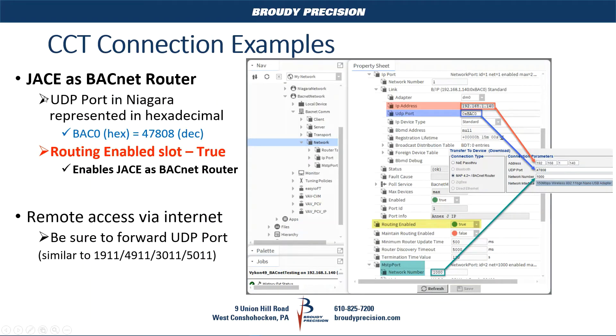If you're going through a JACE, first make sure routing is enabled on the JACE. There is a slot for that under the network settings of your BACnet network, as shown in the property sheet screenshot. You also need the IP address of the IP port being used on your JACE. We're using the standard UDP port — the number may appear in hexadecimal format, which translates to 47808 in decimal. Then go under the MSTP port to get the network number; in our case it's 1000. Enter 1000 and then the network interface you're using to connect to the JACE.